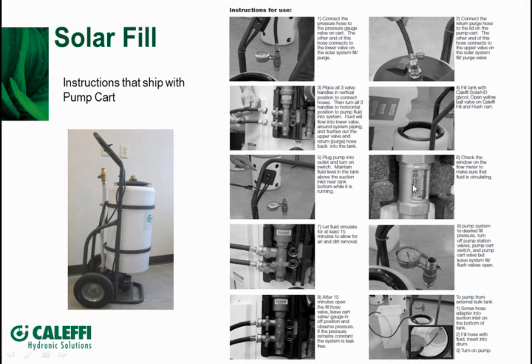You can see our little solar pump station has little flow meters in there, which are handy because you'll see this little dial. You can see it in that picture, but it'll move up to the flow rate. So now you're assuring that you're getting enough flow through that to get a good purge. And you can purge back into a bucket, or in this case, there's a connection on top of our fill cart that you can purge right back into the tank. So now you're just going to keep circulating until the air's out of the system and the fluid comes back nice and clean.